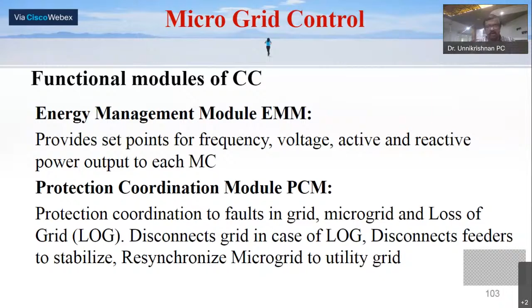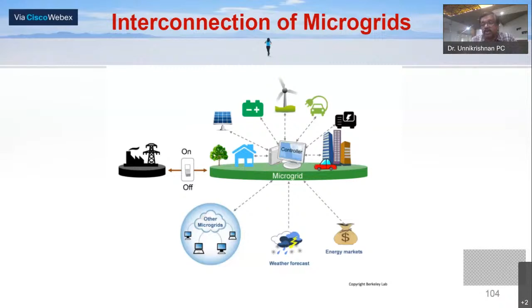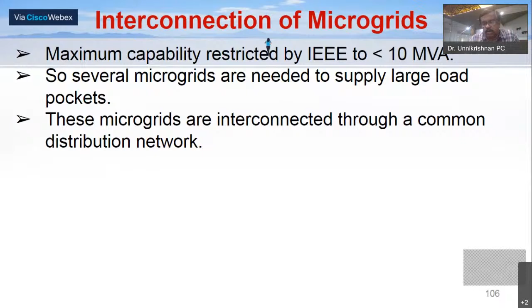Now comes the interconnection of microgrids. When you have two microgrids nearby, you can interconnect them. Firstly, why should we interconnect? That is the first question. If you interconnect many microgrids, you will be able to meet large loads. Such interconnected microgrids, in general, we call a power park. As per the IEEE regulations, the maximum capability of a microgrid is restricted to less than 10 MVA. So if the load is more than 10 MVA, one microgrid cannot cater to the needs. In that case, we have to connect several microgrids to cater to the needs of large load pockets. These microgrids can be interconnected through a common distribution network, or the utility network itself.